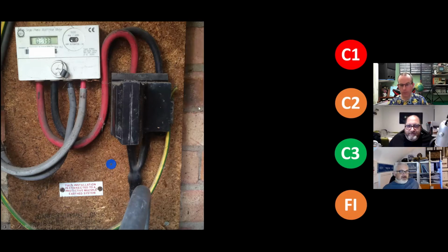Yeah, there you go. So you've got stripped conductors there. Daniel pulled up the tails straight away. Exposed insulation. What about on the right hand side here? Okay, let me go back a bit. So I've got that cut off there. And there's an old earth connection there into the terminal. And this is obviously a new one, a bigger one.